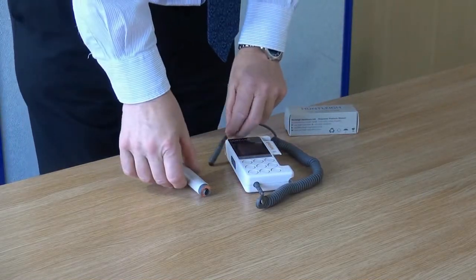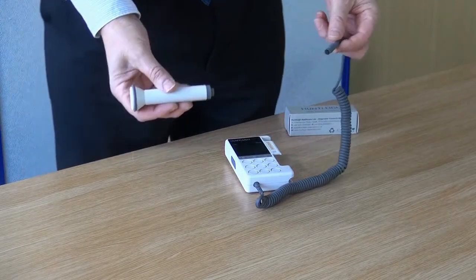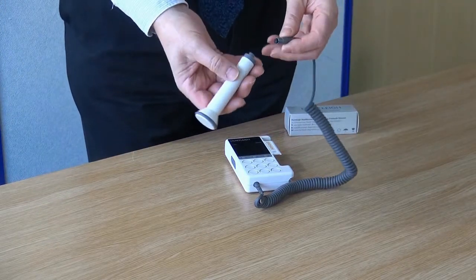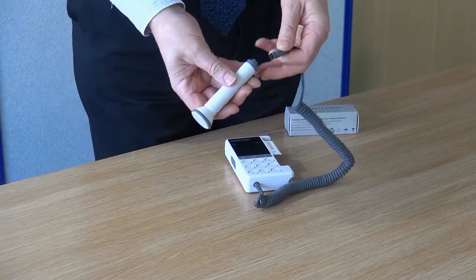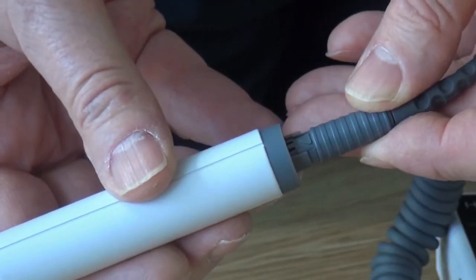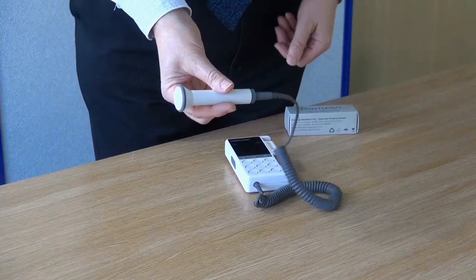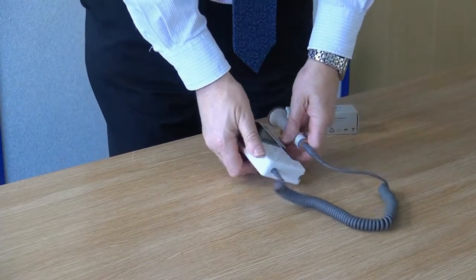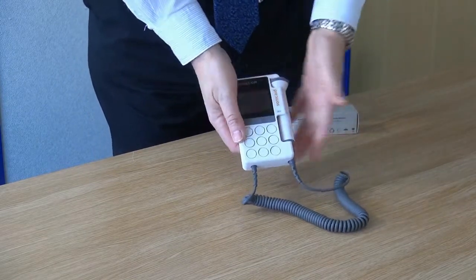Align the connector to the bottom of the probe and rotate until you feel the key system connect. Push the connector into the probe. Once connected, you can place the probe into the probe parking located on the side of the Doppler unit.